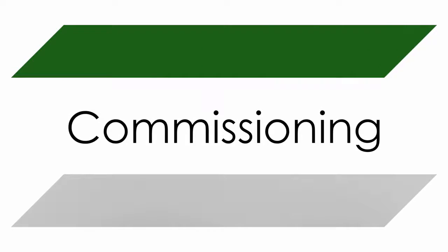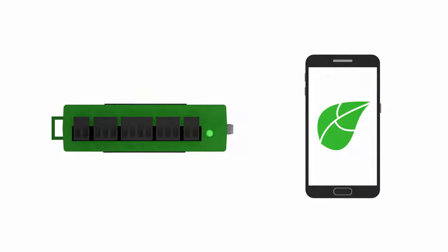Once physical installation and site configuration of the system are complete, it's time to commission the Tigo equipment. Use the Tigo Smart app to test the network connection. When the Cloud Connect is first connected to a network, it will download the configuration file and be ready to start discovery. The discovery process performs a scan for the TS4 units and activates production monitoring for viewing in the Tigo Cloud. This process should be started no later than an hour before sunset.